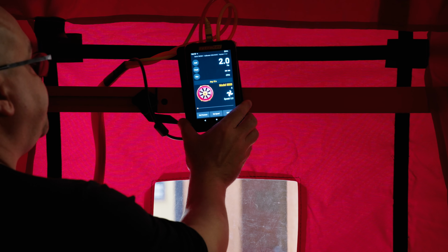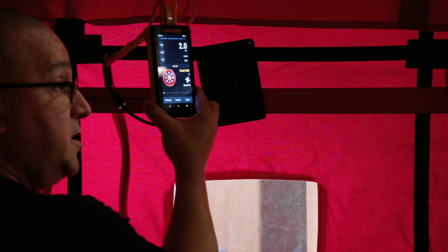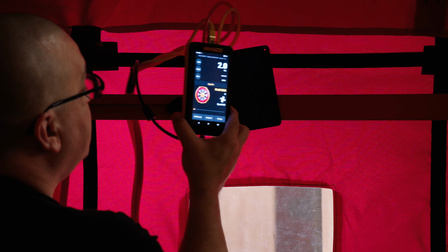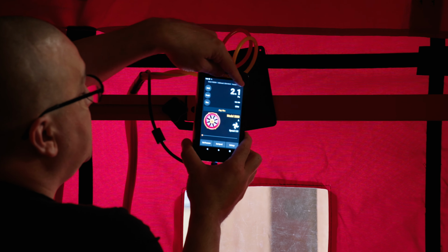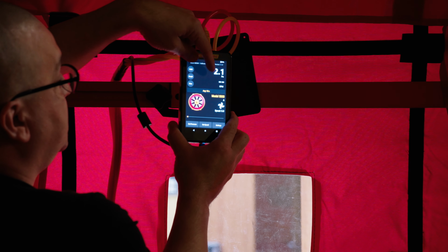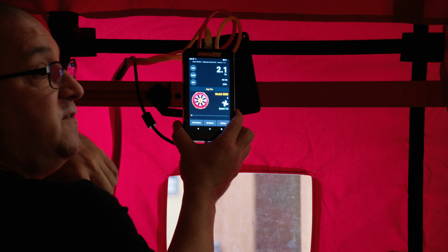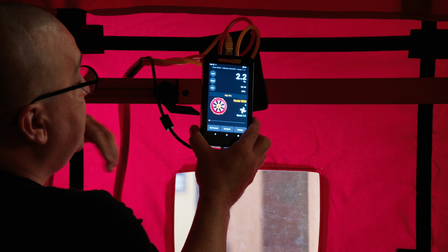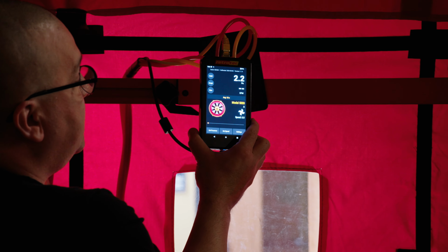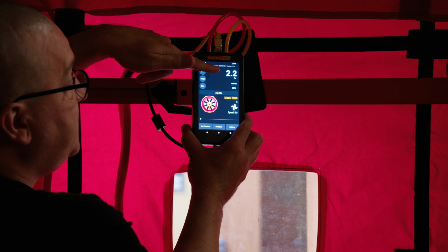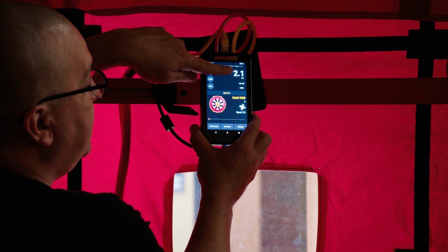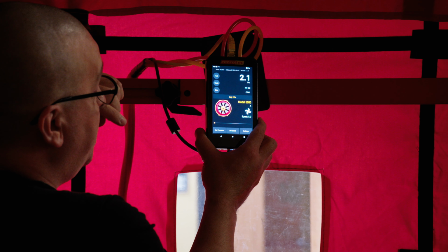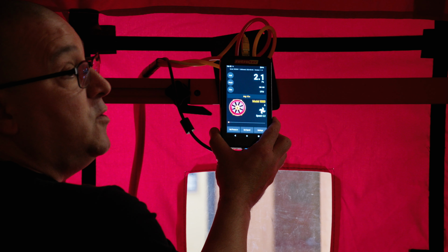So we go with ring A. And this is your actual gauge that shows the pascals, the pressure. Negative 50 pascals is the standard we're using. So we have to get the blower door pulling out enough air to reach negative 50 pascals. And at negative 50, the lower number here, the CFM, is your blower door number.